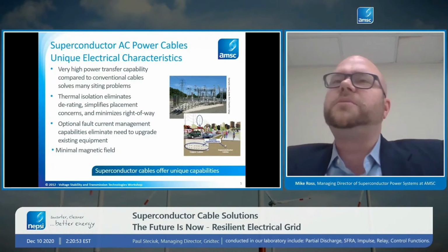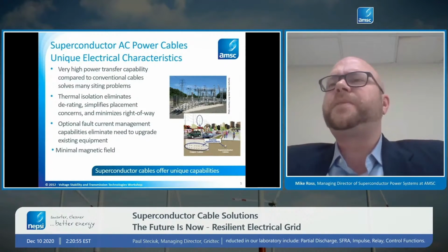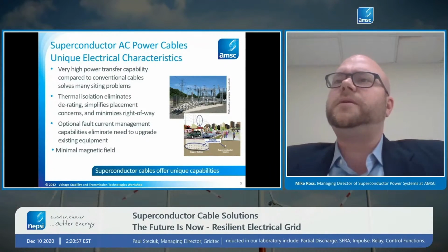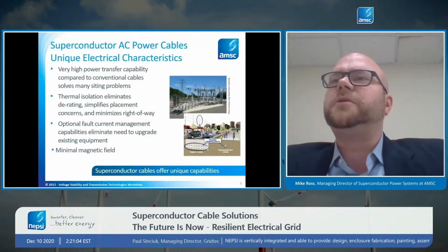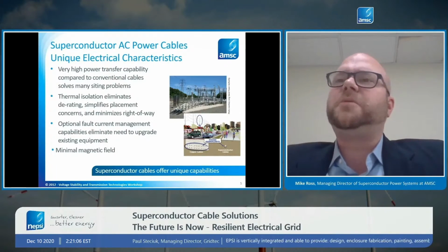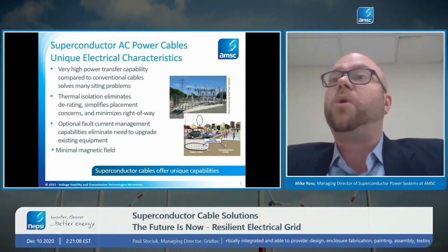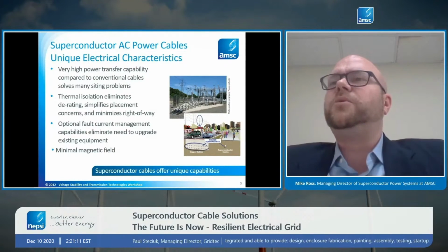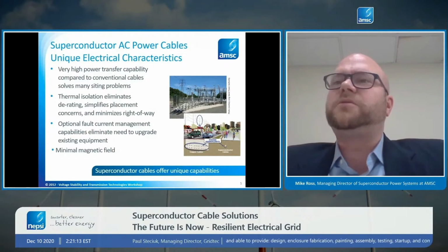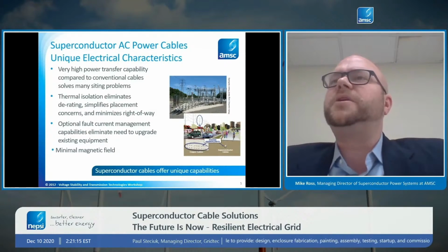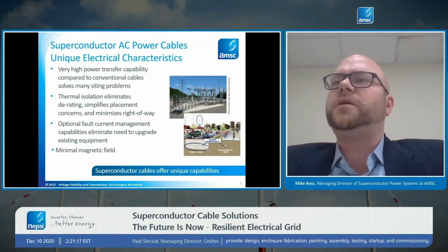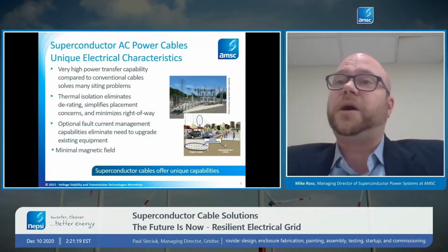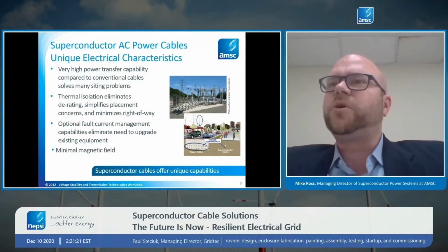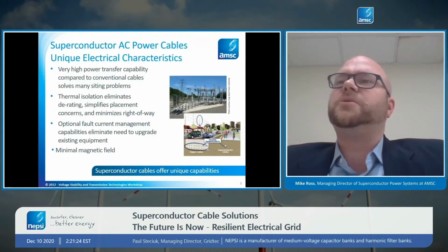The only reason that we limit ourselves to 4,000 amps is that we still have to connect to the existing grid, and that existing grid is going to use conventional equipment like breakers and bus bars. It's almost impossible to buy breakers and bus bars and other equipment that's rated at more than 4,000 amps. So while we can move huge amounts of current through our cables, we usually limit ourselves to what ancillary equipment we can buy, which is about 4,000 amps. But it's still 4 times what conventional cables can move.